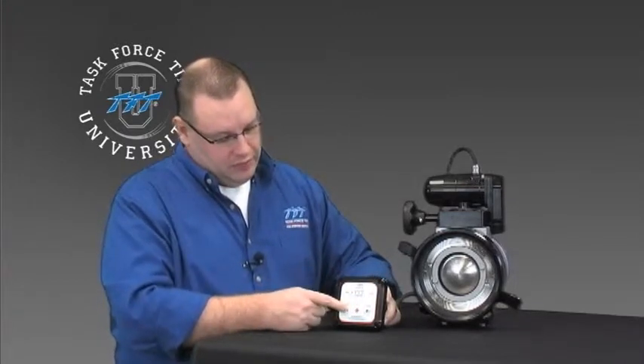From the factory, they ship in standard manual mode. What that means is as you hold the button down, the valve moves. Take your finger off, the valve stops. It's nice for being able to feather the valve for whatever type of application you need, opening and closing it to whatever opening that you want.